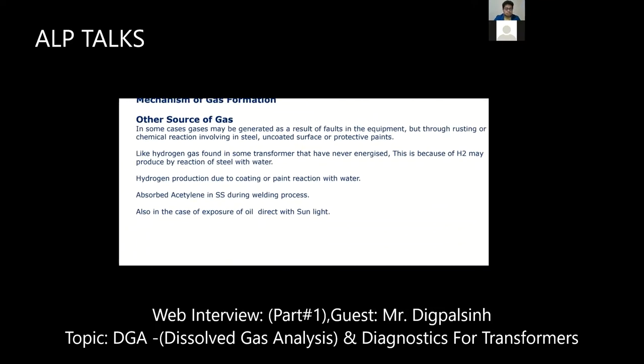Then what happens when you weld at the time of manufacturing? I have mentioned stainless steel, but it can be mild steel, stainless steel, or any type of SS. At the time of welding, it absorbs some C2H2, acetylene gas, inside the material, and this gas will also be liberated by the material at the time of transformer operation. So it is not a major issue, but sometimes acetylene is found because it was absorbed by the material during the welding process.